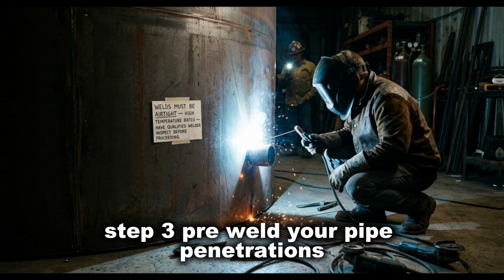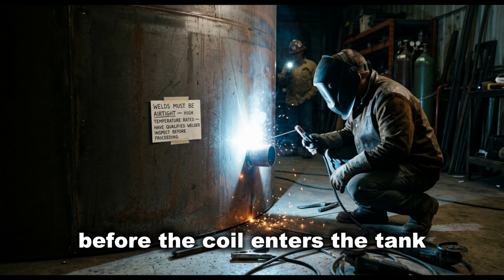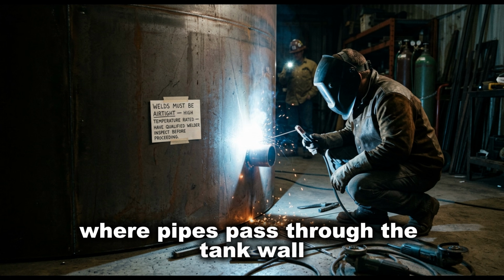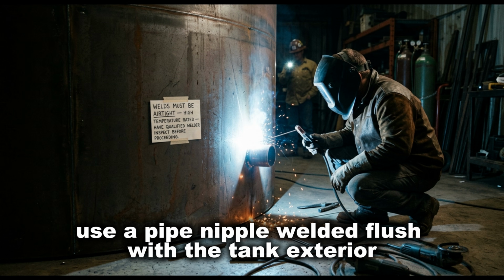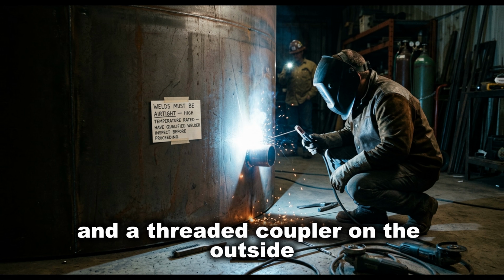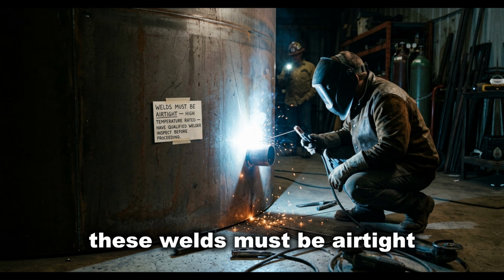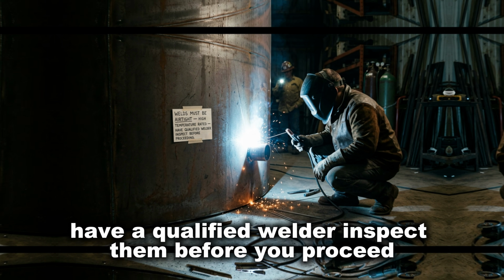Pre-weld your pipe penetrations. Before the coil enters the tank, weld the entry and exit points where pipes pass through the tank wall. Use a pipe nipple welded flush with the tank exterior and a threaded coupler on the outside. These welds must be airtight and rated for high temperature. Have a qualified welder inspect them before you proceed.